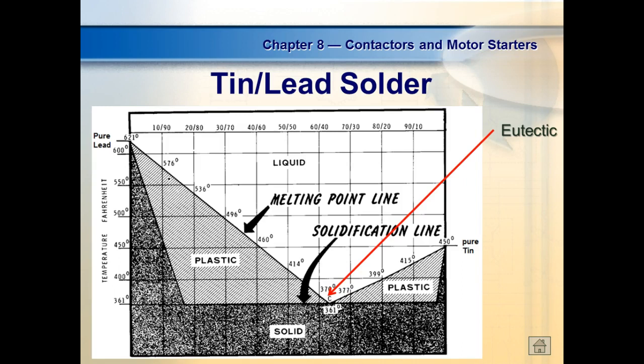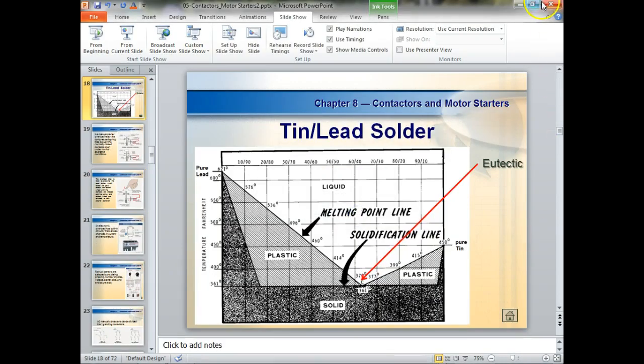You understand that? Well, what do we have to do now before we can reset this thing? Yeah, you gotta let it cool down. So these heater overloads, the only disadvantage of them is you gotta let them cool down before you can reset them. So normally they have some type of reset on the side. They're required now to have something that indicates when the overload is tripped.